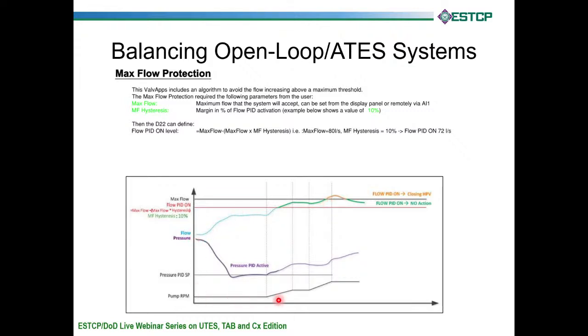As you can see, this little diagram here shows both the pressure set point and the flow set point. Our max flow set point is up here, and we have a hysteresis here that you have to program in. If the flow rate gets above that hysteresis, the PID comes on and it starts counting to see what the rate of increase in flow rate is. Once it breaks the maximum flow set point, the valve starts closing based on the PID having been counting for this whole period, and it gets it back under control.